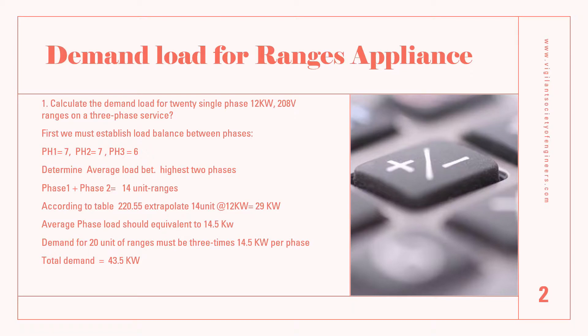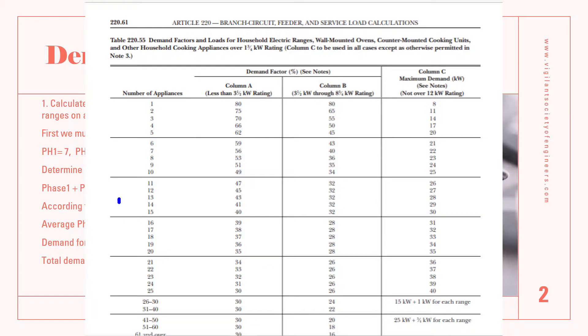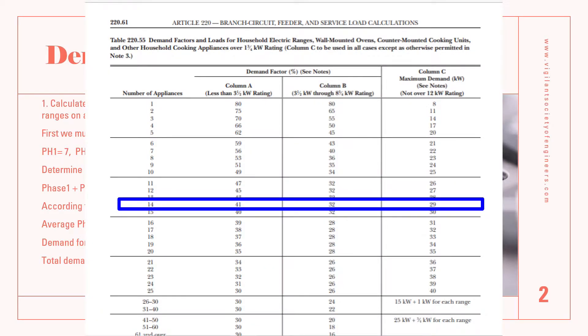Next, we find the average between two phases for the kilowatt value required. Phase one and two would have those two values, so in total we have 14 units of ranges. If we go to Table 220.55, we can extrapolate a value for 14 units at 12 kilowatt.